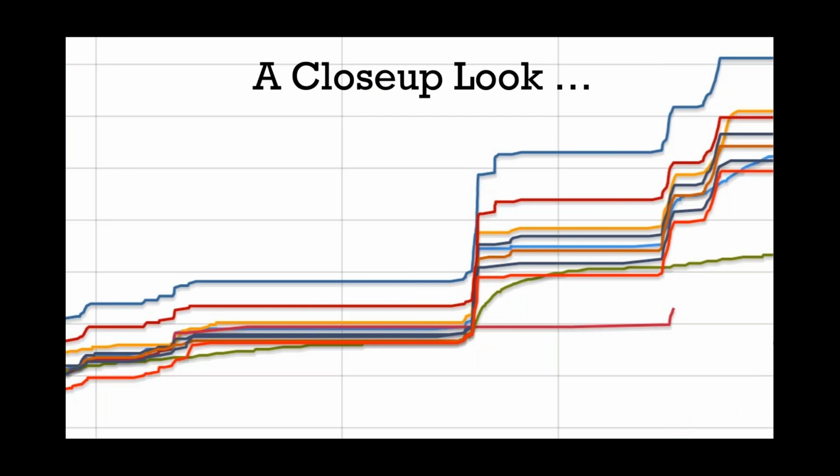If we take a closer look at that last little graph, we can see that way back over on the far left-hand side here, the green line had already flattened out. And then about the middle, it gets even worse, a little arching in there. So, there's a clogged funnel that's leaking through, but it actually started way back on the far left-hand side. We see the same thing on the right-hand side, about the middle of the light blue line. It starts just a gradual climb rather than steeper inclines like the rest of the measurements are.